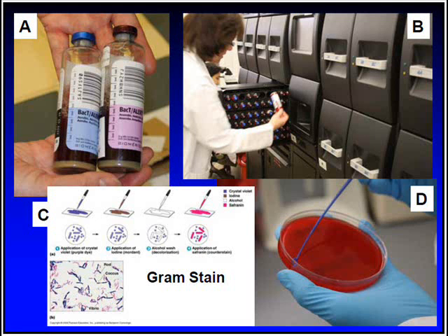These photos were taken from our clinical microbiology laboratory. In the upper left photo, panel A, we have a set of blood culture bottles. The blue top bottle on the left is for isolating aerobic pathogens, and the bottle on the right for anaerobes. At the base of the bottle, there is an indicator which signals microbial growth in the bottle by indirectly measuring the CO2 production through changes in the acidity in the media. The indicator changes from green to yellow. Yellow is indication of a positive bottle.